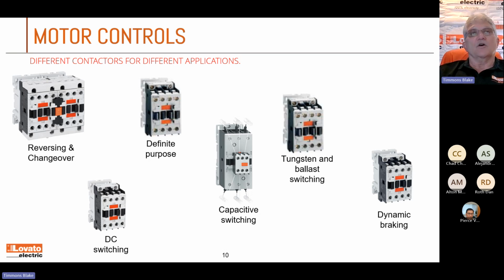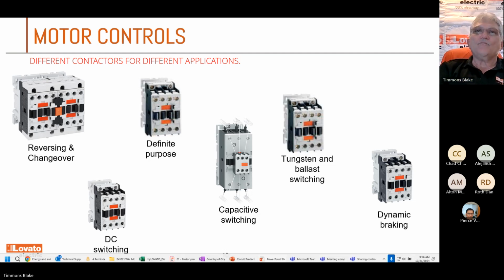We need them to go a long time. But sometimes you're doing these things for your home unit, your AC unit at the house. And we can derate these things by calling it a definite purpose contactor. You'll see that I can take what would normally be a 9 amp contactor for a motor, and I can almost get 20-something amps out of it because you promise it's definite purpose, and you're only going to use this for 250,000 cycles, not more. So that's how we're able to derate it.